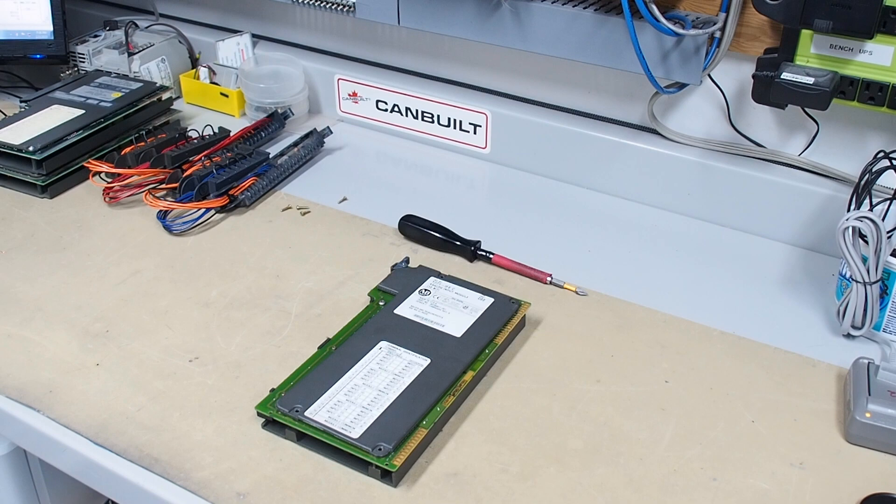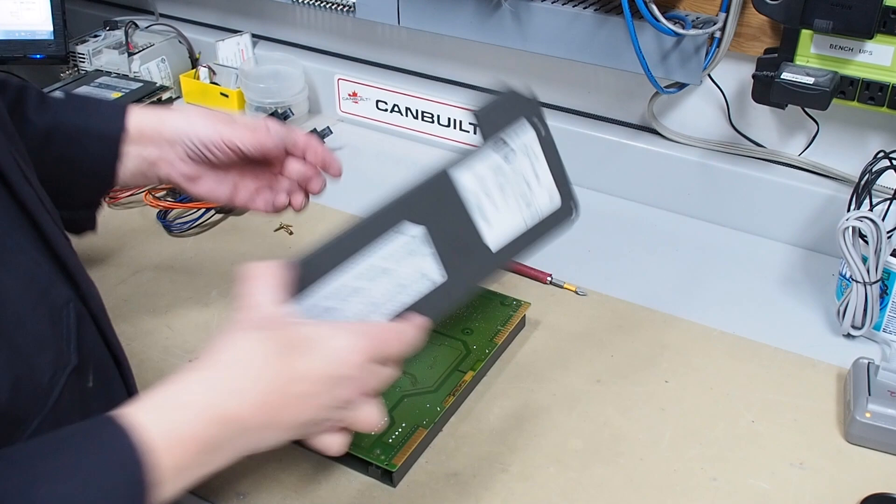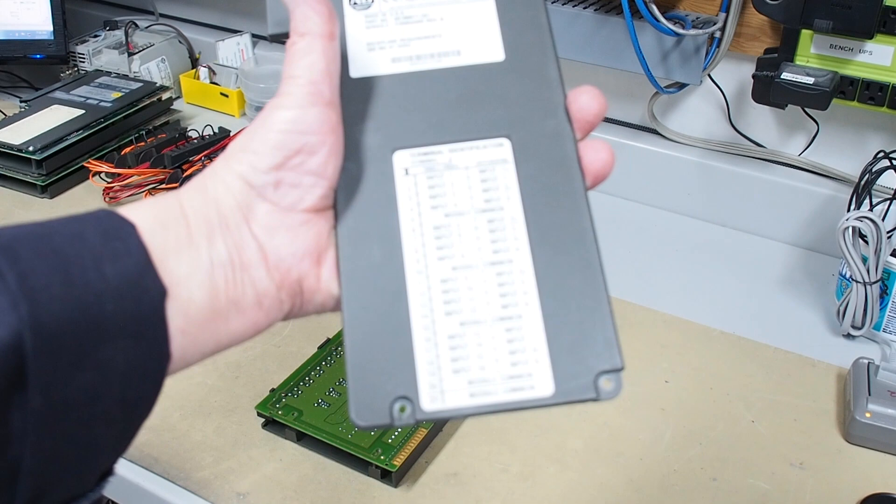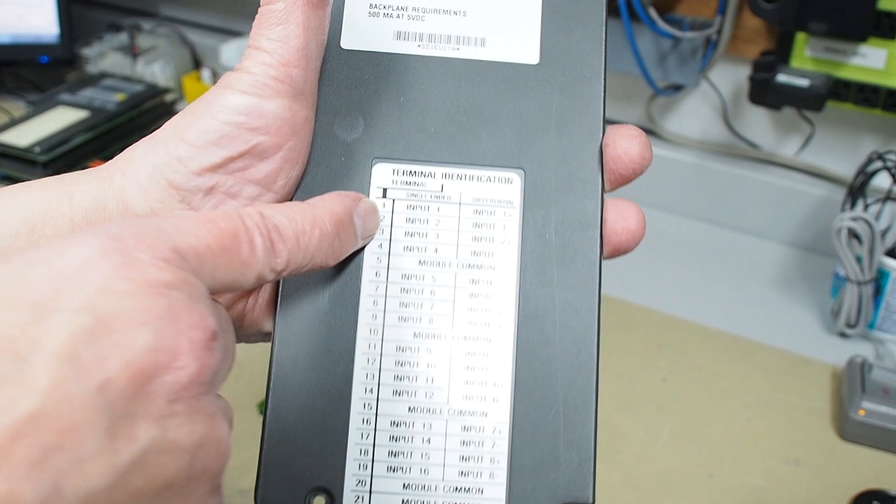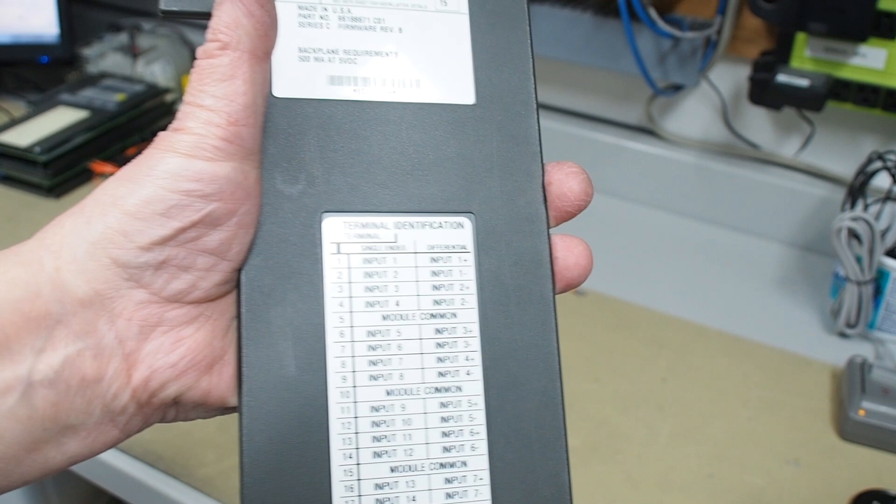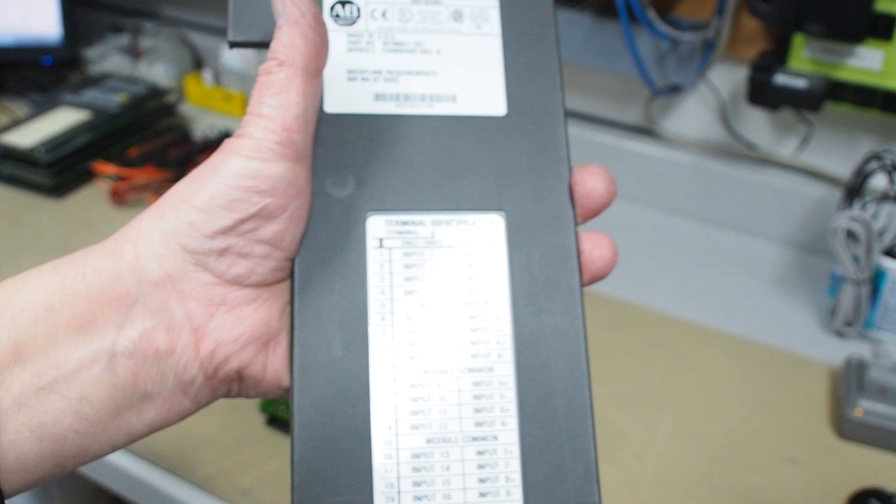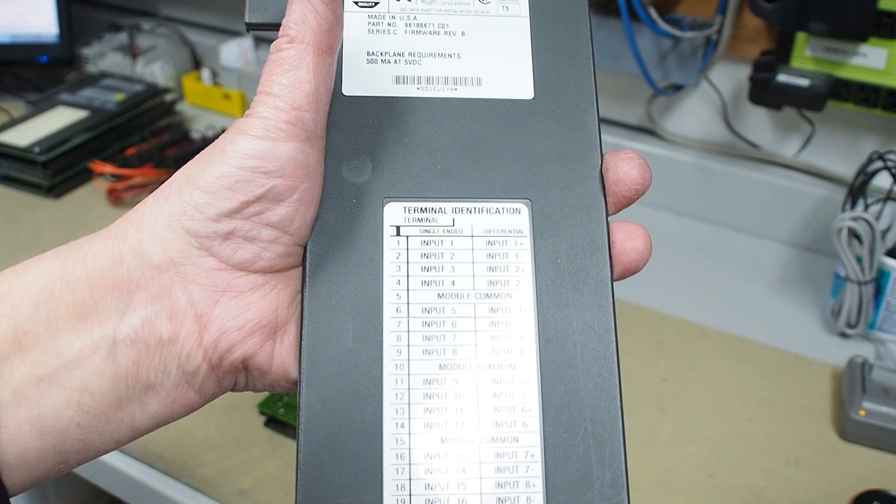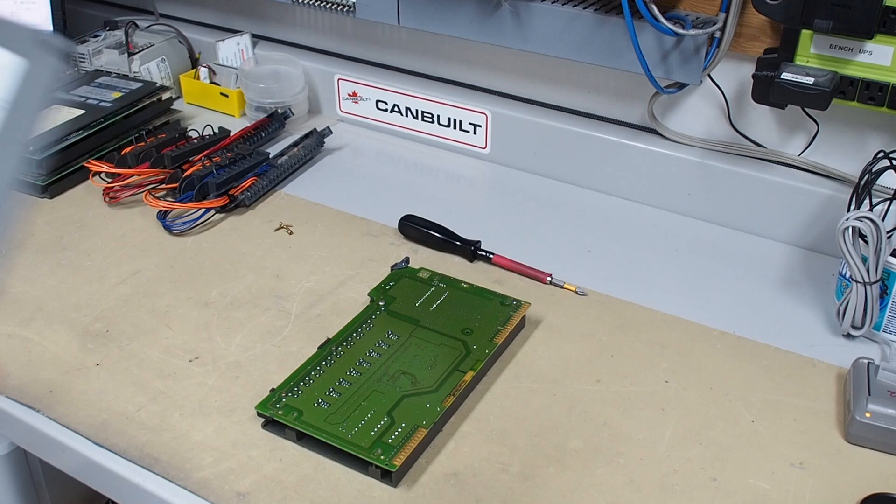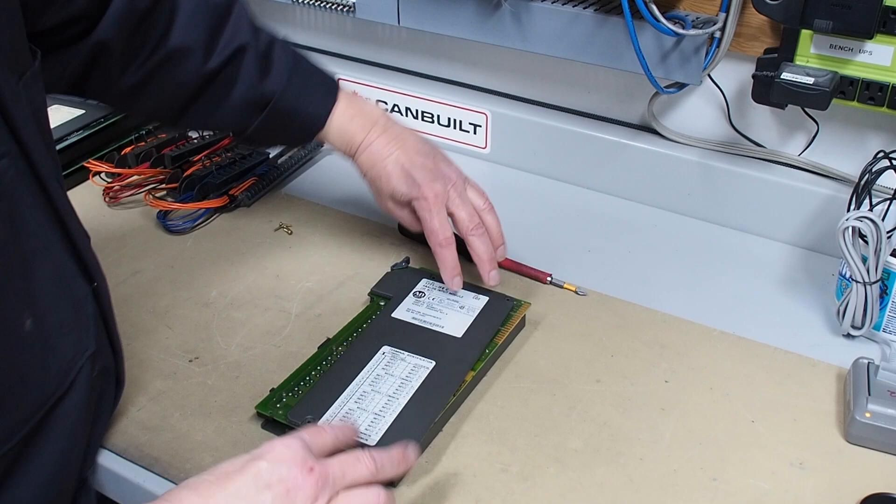Here we are on the bench. I've taken the four screws out of the cover, so here's our card. As you hopefully can see, depending upon the light, we've got four inputs common, four inputs common, four inputs common, and two commons at the bottom. Reading through the documentation, all of the commons are common hooked together on the card. This is not an isolated situation.